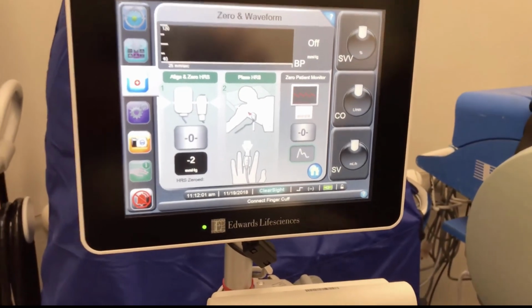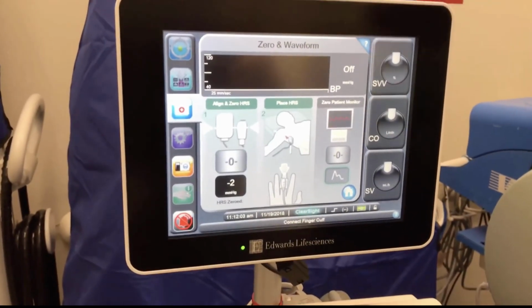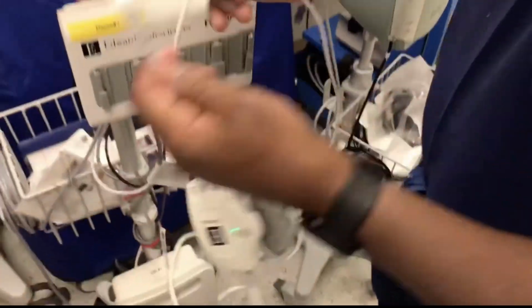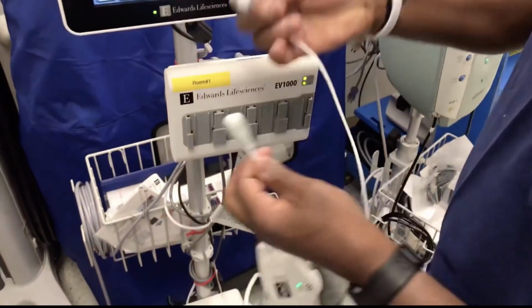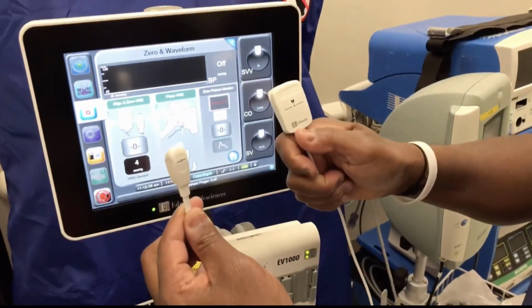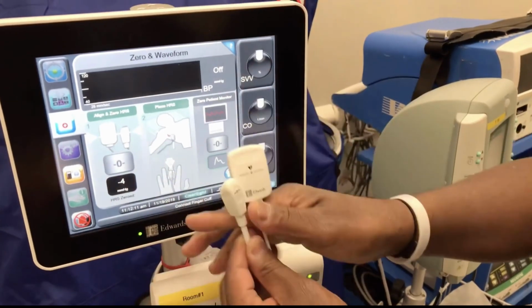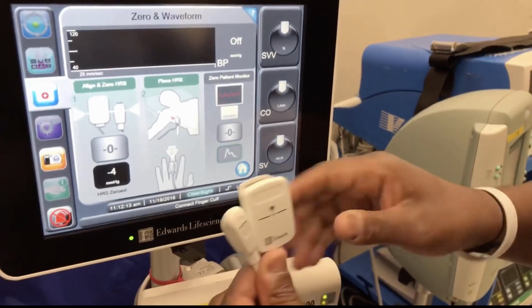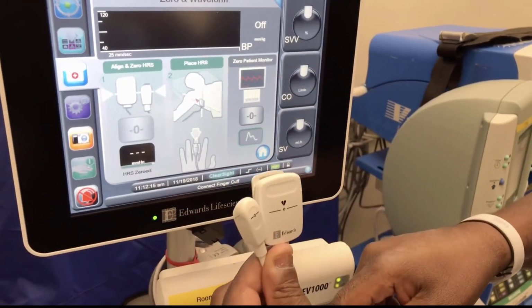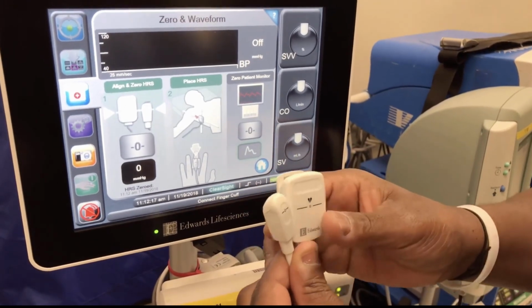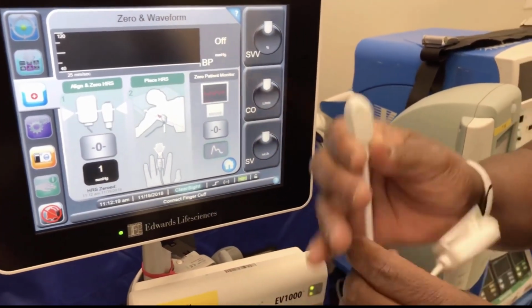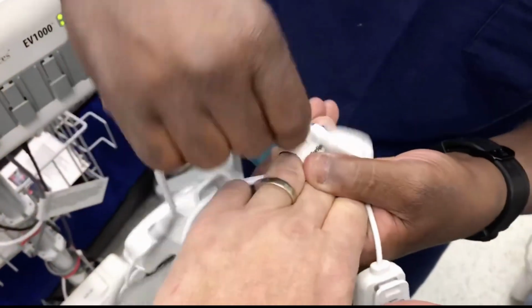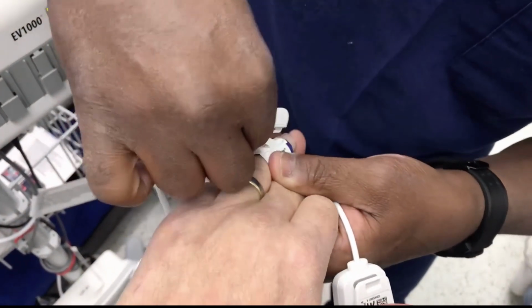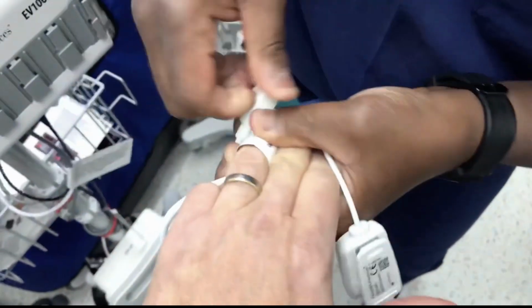Now it wants you to zero this out. To zero, you're going to take the heart reference sensor end of it and the finger end of this. This is basically a transducer. You're going to zero these 2 out by putting them together and pressing 0. It is 0. Once zeroed, you're going to take the finger end and connect it to the finger slot here on the slot.